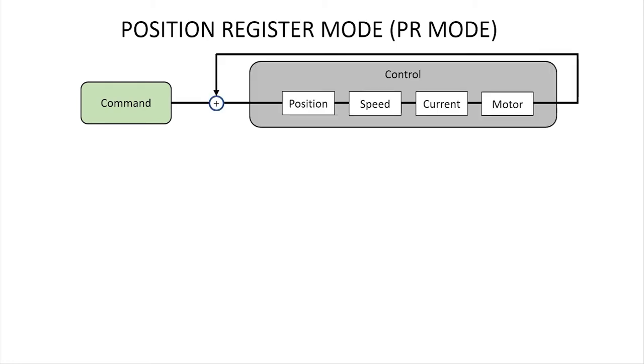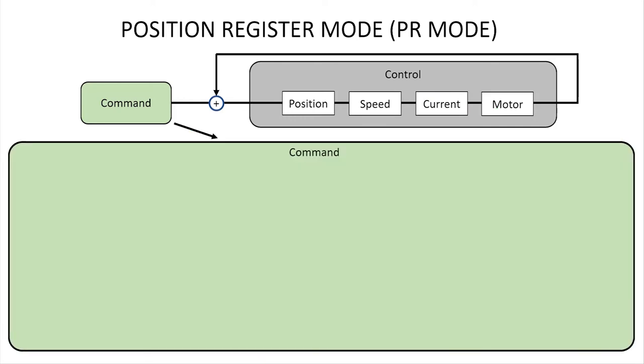Understand that Position Register Mode is really two parts. There's the command portion where you tell the drive what you want it to do and the control portion where the drive does everything it can to maintain the position, speed and current and apply that appropriate signal to the motor.